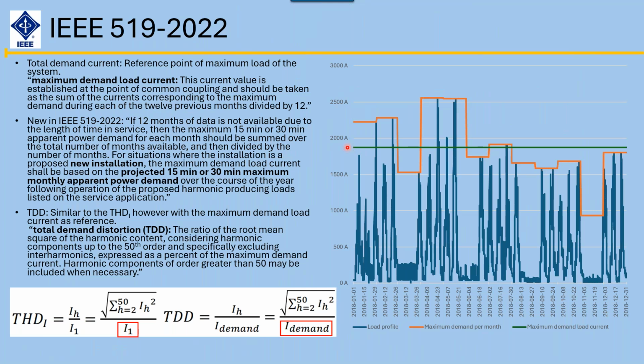Okay. And what they've done now in the standard, which is good, is they base everything on the total demand distortion versus THDI. A lot of customers and a lot of my competitors will go, oh, you've got 40% THDI. The reality is I don't care, because THDI is based on the total of your harmonics, for the 50 harmonics, over the fundamental current. So in this case, my demands are very high and very close together, so the fundamental current is going to be a large number. If I go to this section right here, this current's very low. The harmonics are going to be fairly constant, so I'm going to get a very large THDI, and it's going to give me a false positive.